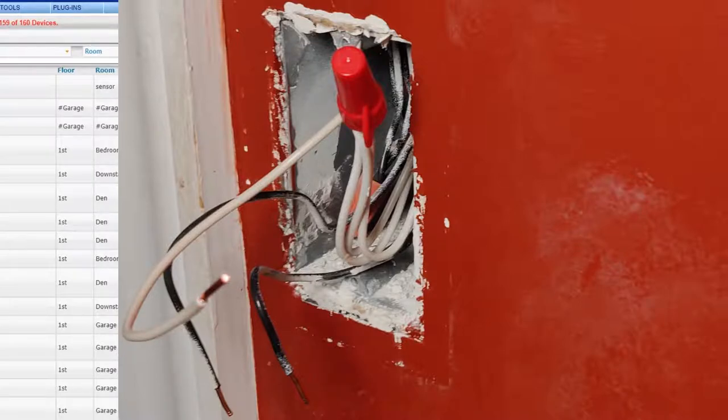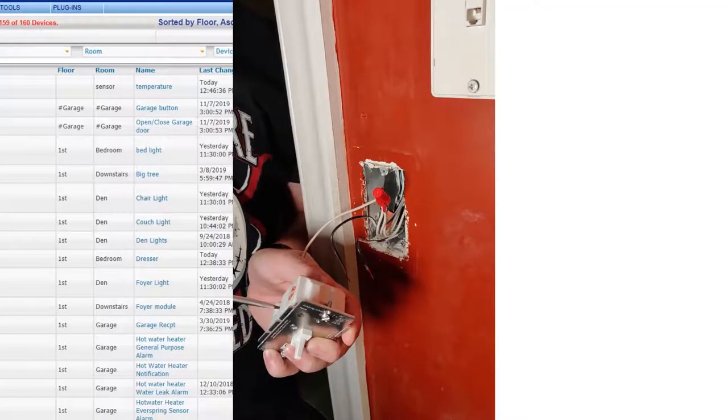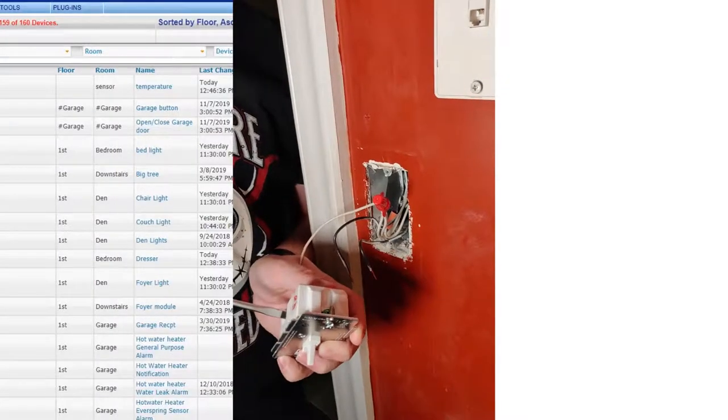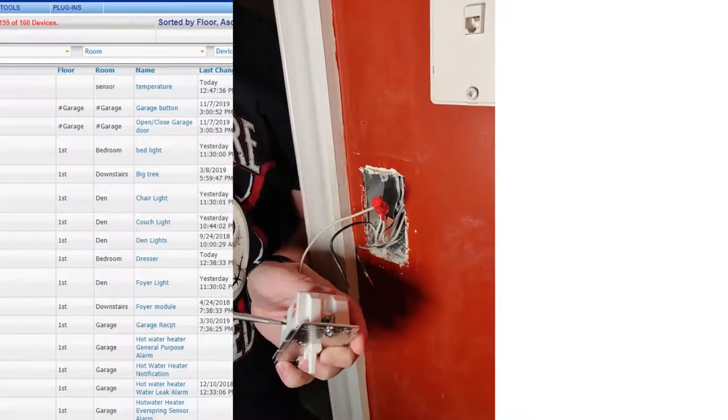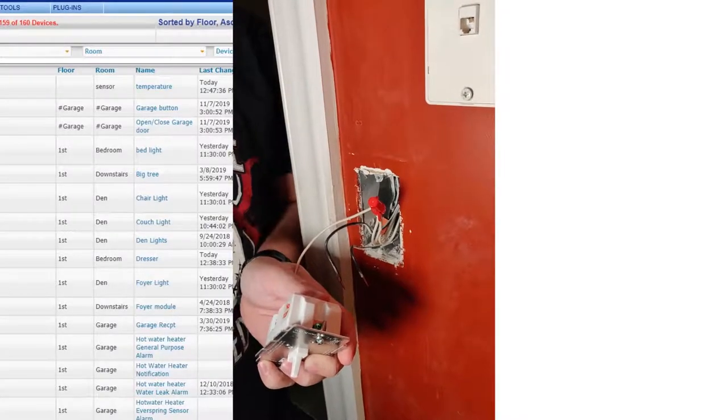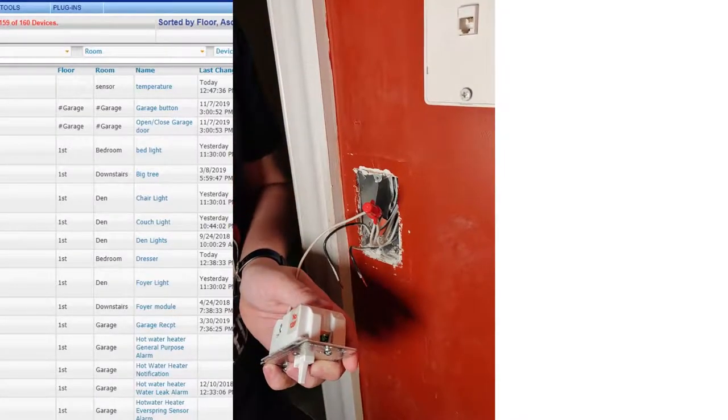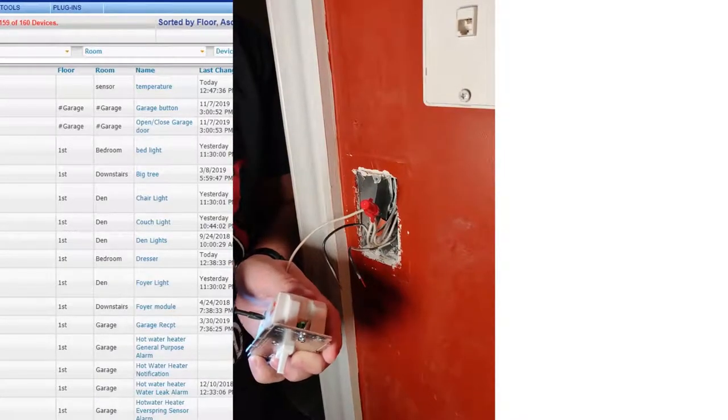Going into this new one, we will have to add a pigtail. And what I mean by a pigtail is, just a picture here, I've added another wire to the white wire bundle. And this is for American installation, of course. So what I've done is, now I've got the three wires, the white neutral and then the two hot wires.